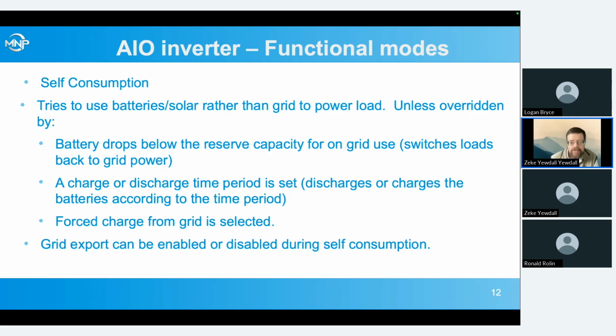Another way to override it is to set a charge or discharge time period. This we'll talk about a bit more when we talk about the time periods, but essentially, anytime we have a charge or discharge time period, this overrides self-consumption, and instead, it will charge at the set rate up to the set state of charge, or discharge at a set rate down to a set state of charge.